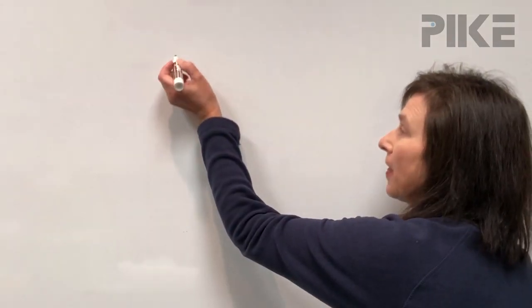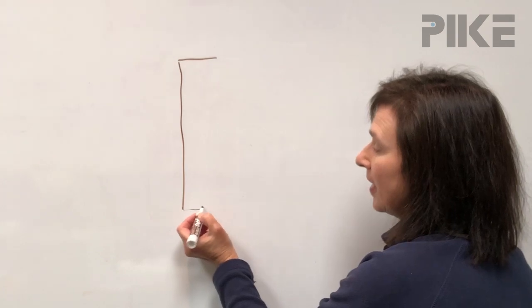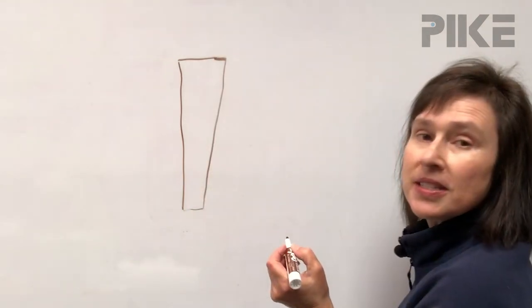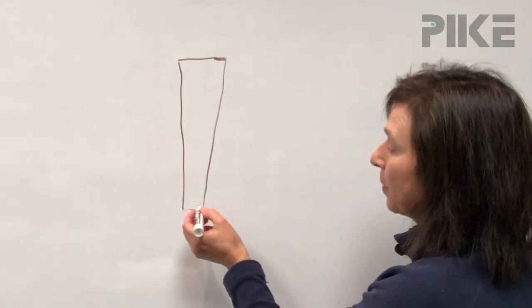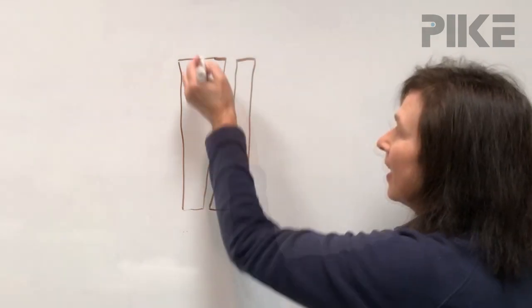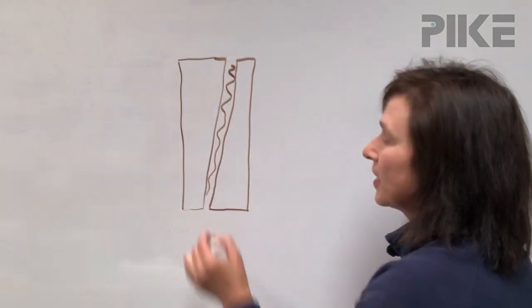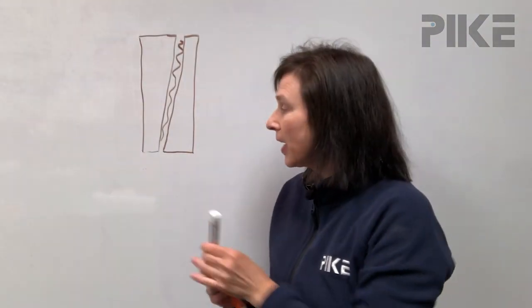Let's take a look at how to assemble a liquid demountable cell with wedge windows. Now with wedge windows we're going to have a thick and a thin side, so when assembling the cell we need to make sure we go from thin to thick and thick to thin. In between we're going to have our spacer.